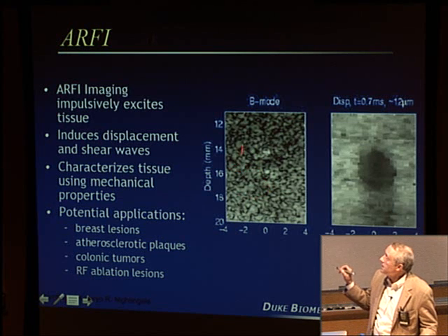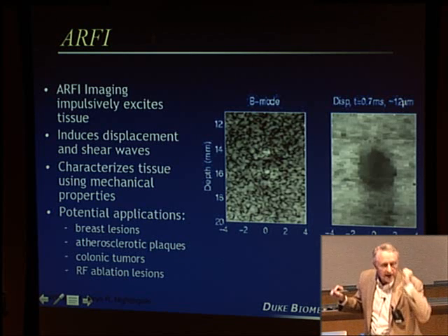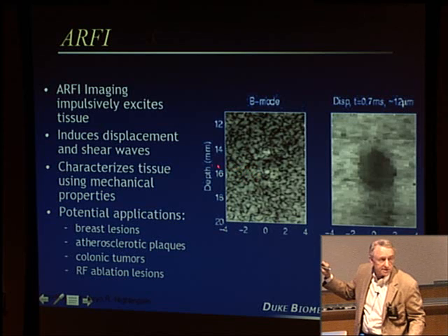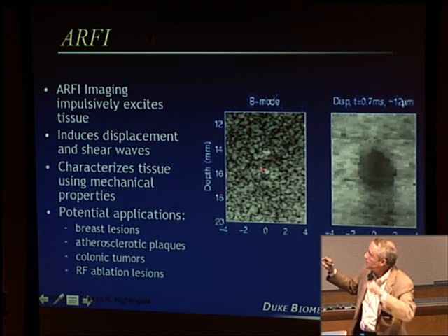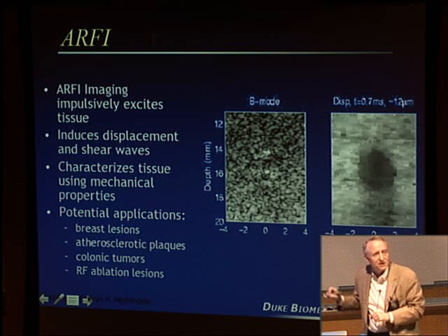So what I'm saying is I could take a beam up here, focus down to a point here, crank up the intensity, give a blast of ultrasound, and at that focal point where the intensity is the highest, there's going to be a nice little radiation force push, as if I put my finger into the middle of this right here at 16 millimeters and pushed quickly. Okay?